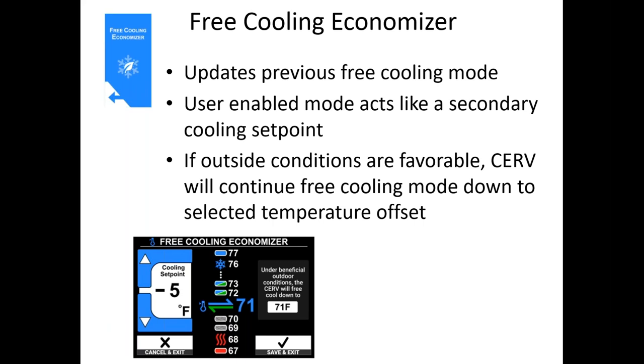So in the swing season especially, if you have this set, the CERV may be doing a lot of free cooling at night and really not have to do any ventilation at all during the daytime, because the pollutant level has been brought so low during the nighttime that it can really coast through the daytime when it may not be as favorable to do ventilation. So this can help with efficiency quite a bit as well.